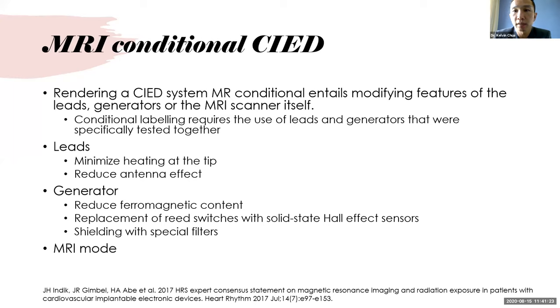So rendering a device to be MRI conditional actually requires the leads and generators to be specifically tested together. That's very important for the audience out there. If you have a device and two leads, and only one of them is MR conditional, and they were not tested together in the system, this system is still MR non-conditional.